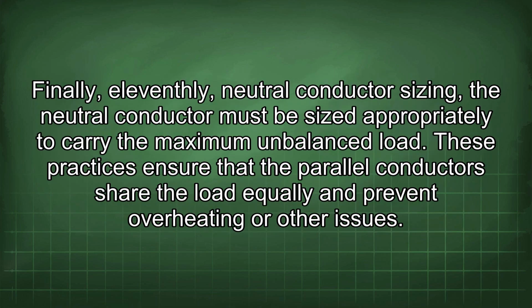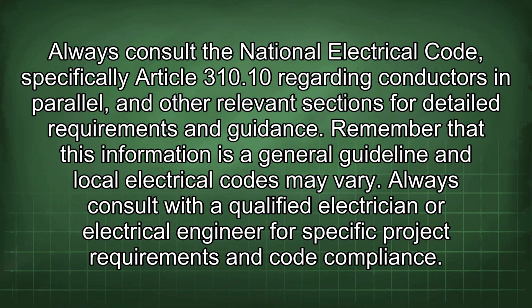Finally, eleventhly, neutral conductor sizing. The neutral conductor must be sized appropriately to carry the maximum unbalanced load. These practices ensure that the parallel conductors share the load equally and prevent overheating or other issues. Always consult the National Electrical Code, specifically Article 310.10 regarding conductors in parallel, and other relevant sections for detailed requirements and guidance. Remember that this information is a general guideline and local electrical codes may vary. Always consult with a qualified electrician or electrical engineer for specific project requirements and code compliance.